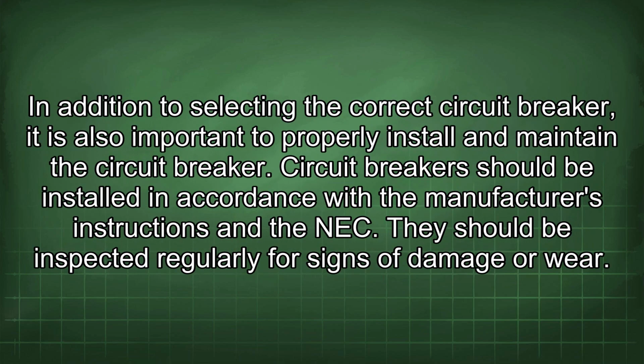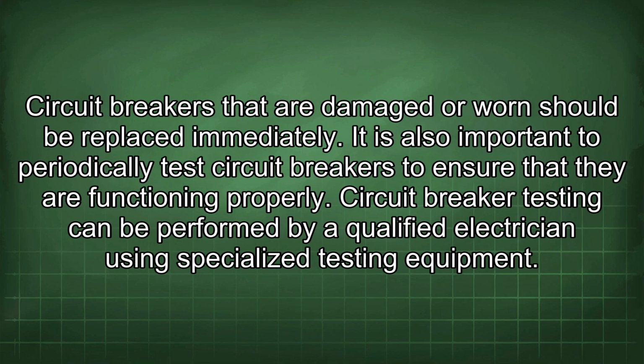In addition to selecting the correct circuit breaker, it is also important to properly install and maintain the circuit breaker. Circuit breakers should be installed in accordance with the manufacturer's instructions and the NEC. They should be inspected regularly for signs of damage or wear. Circuit breakers that are damaged or worn should be replaced immediately. It is also important to periodically test circuit breakers to ensure that they are functioning properly.